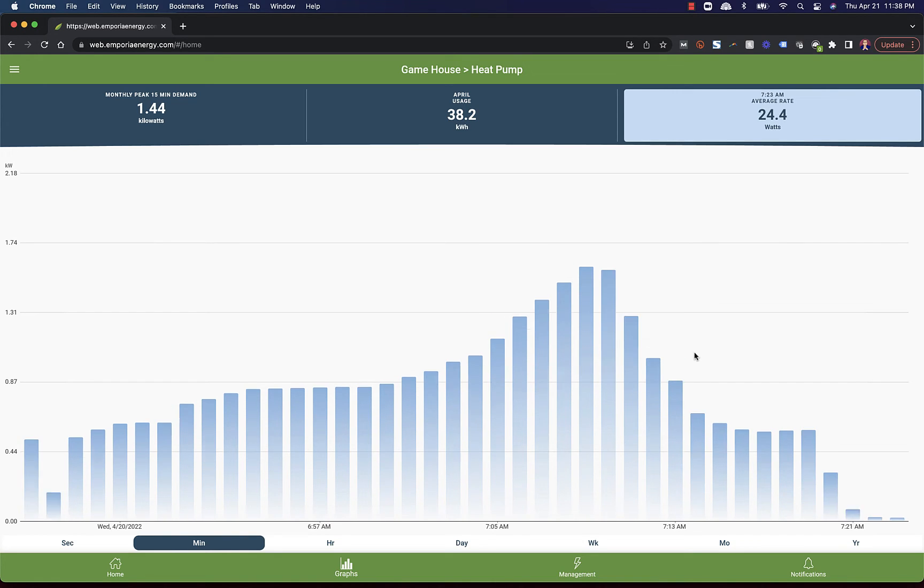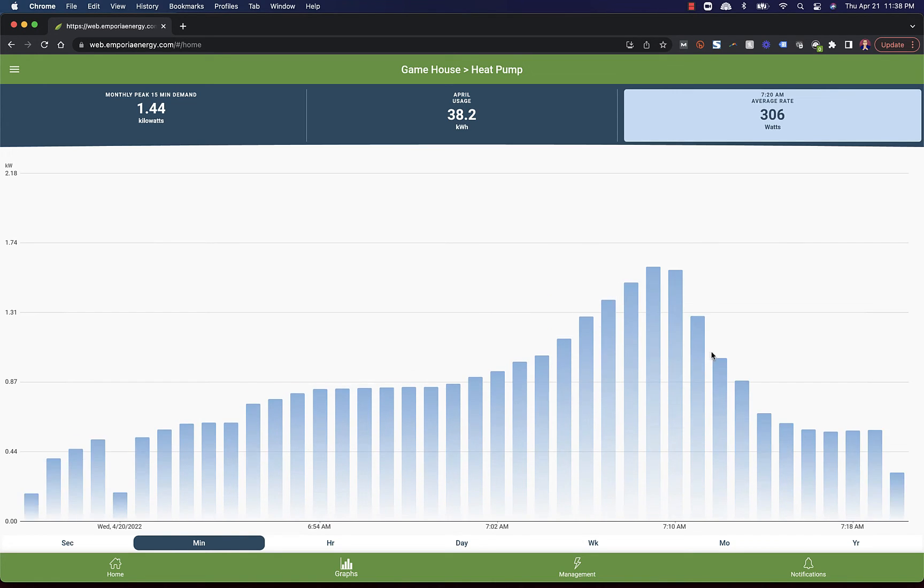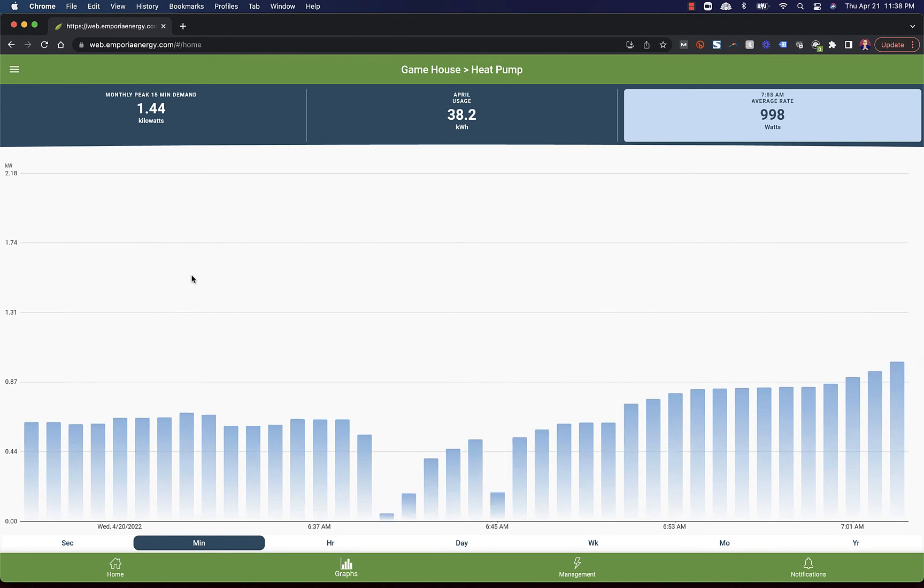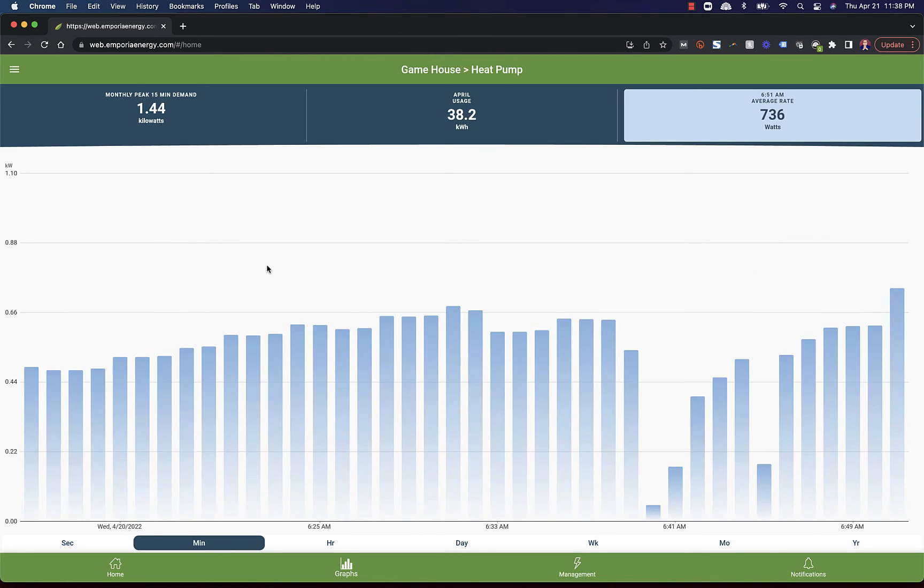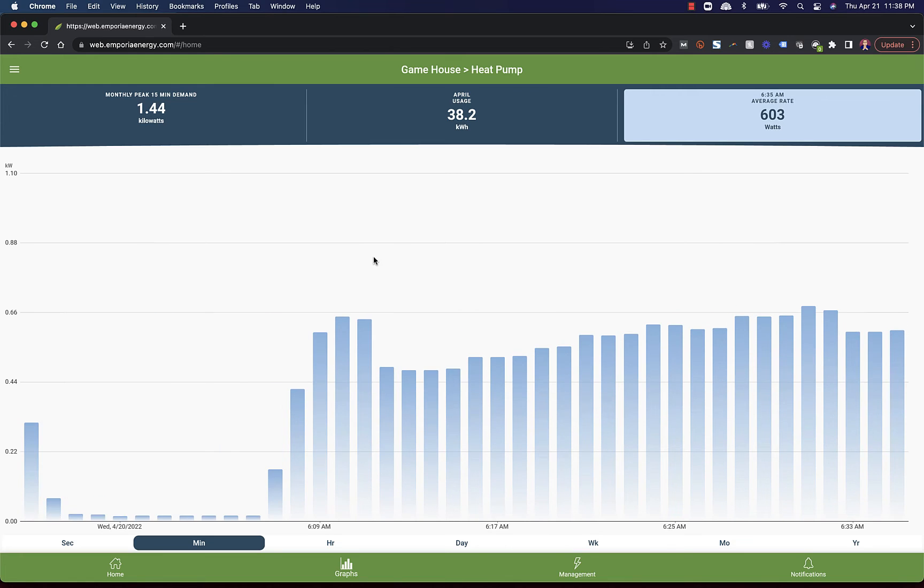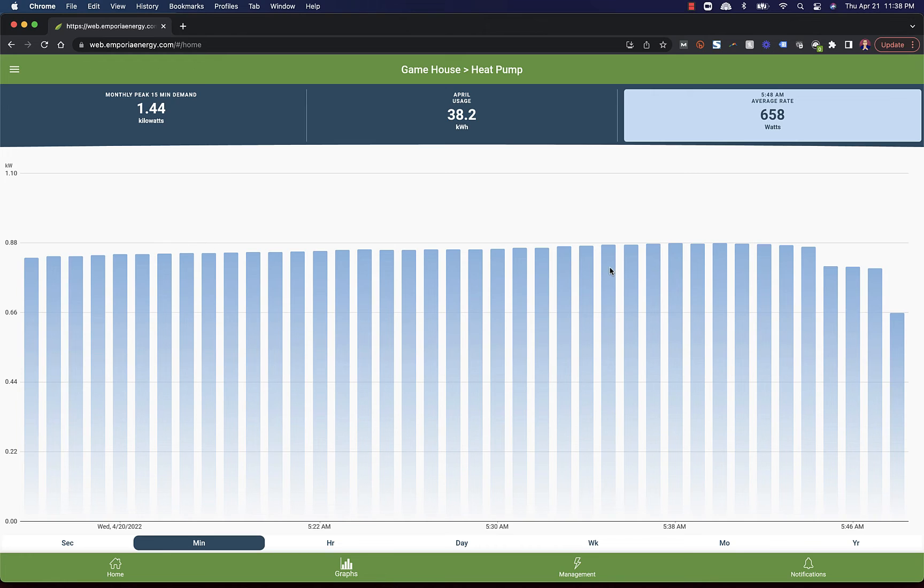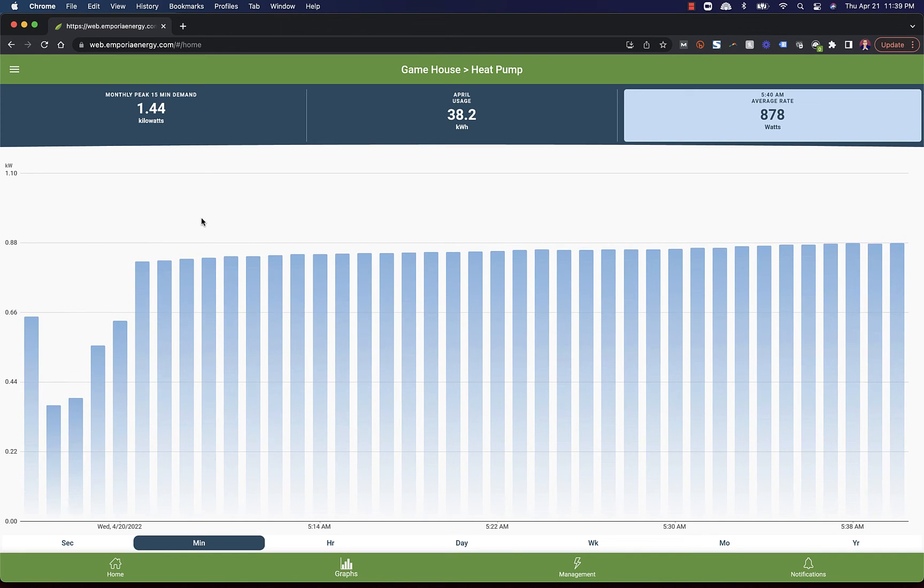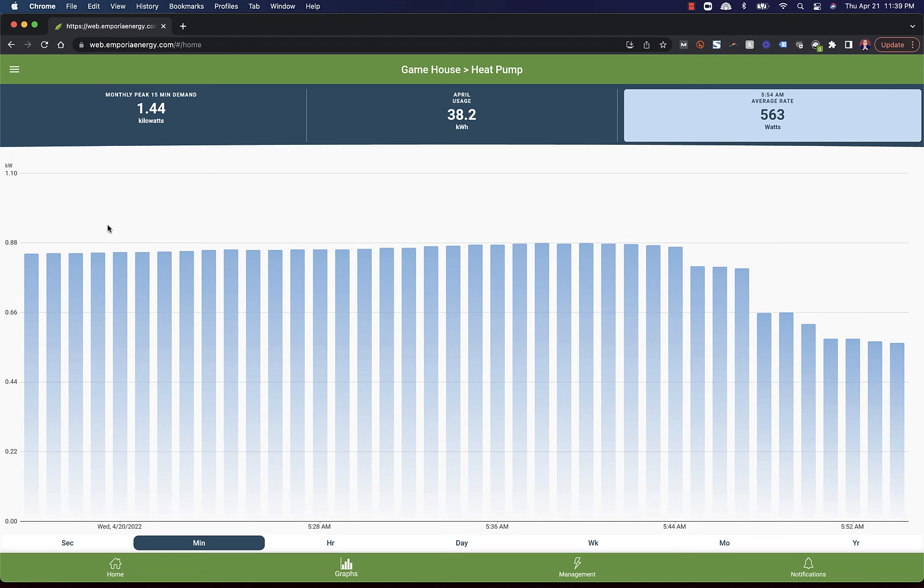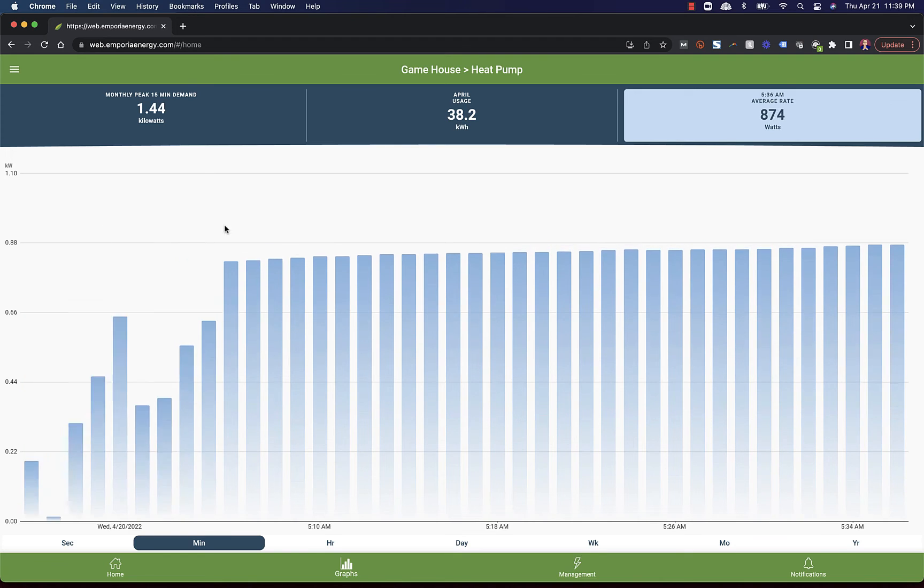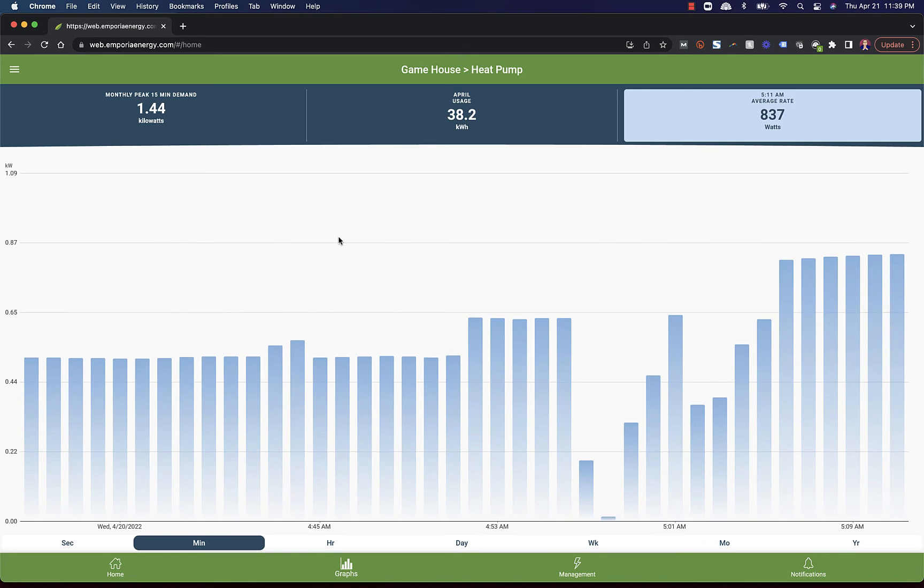It ramped up some. This is probably when I woke up and turned the temperature up. Should not be using setback, but here I am using a degree or two of setback. So was it 6:09 it started? So that system ran for over an hour, an hour and 10 minutes. That's incredible. This is really, really nice to see. And this makes me very impressed with this system. And here we are. The system needed a fair amount of power to do its job. But nothing crazy. 650. This is two-thirds of a ton. And it's a one and a half ton system. And it'll do a little bit more than one and a half. But look, here's another really long cycle. An hour long cycle.